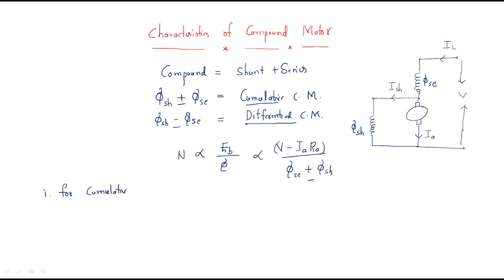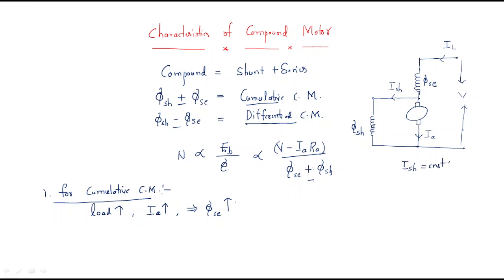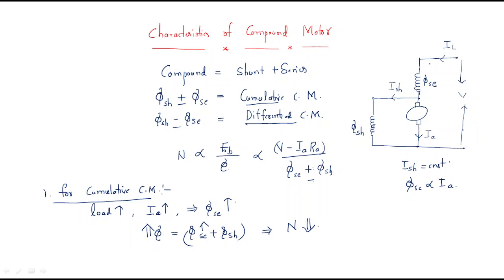First case: cumulative compound motor. In a cumulative compound motor, if the load increases, the armature current increases. When the armature current increases, the series flux increases. The shunt flux is always constant, and the series flux is proportional to the armature or load current. So the total flux — which is series plus shunt — increases, and whenever the total flux increases, the speed decreases.